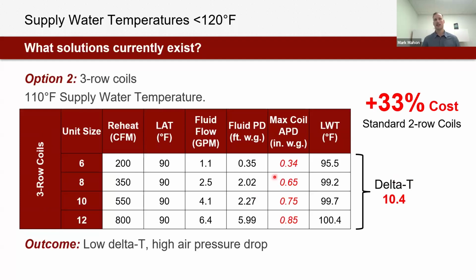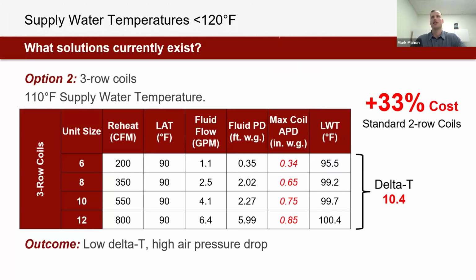And so what is the alternative? There's such a diminishing return on bumping GPM when you're tight like that. Absolutely. We're looking at what I would consider and call coil saturation. If we were to look at a curve, I'll draw it quick. Hopefully it doesn't look too bad. But when we look at GPM on the x-axis here, and capacity on the y-axis here, I'm not going to even be able to write those legibly, so we won't see it.